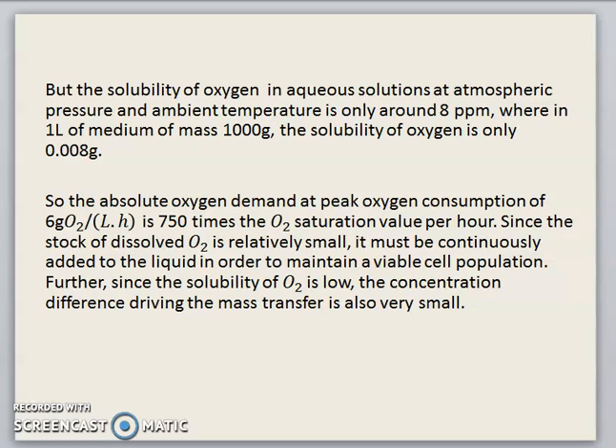However, the solubility of oxygen in aqueous solution at atmospheric pressure and ambient temperature is only around 8 ppm. In 1 liter of medium of mass 1000 grams, the solubility of oxygen is only 0.008 gram — which is very small. So the absolute oxygen demand at peak consumption of 6 gram oxygen per liter per hour is 750 times the oxygen saturation value per hour. Since the stock of dissolved oxygen is relatively small, it must be continuously added to the liquid in order to maintain a viable cell population. This can be done through a sparger — which is the aeration. Since the solubility of oxygen is low, the concentration difference driving mass transfer is also very small.